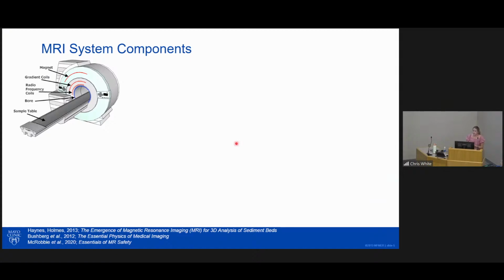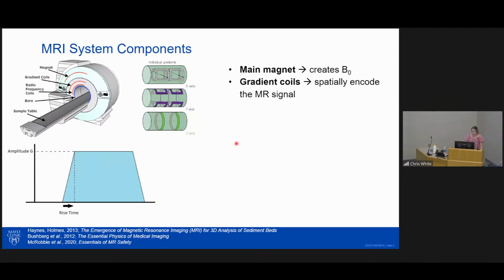So there are three main components of an MRI scanner that I'm going to talk about today. The first is the main magnet, which creates the very strong static magnetic field called B0. The second are the gradient coils, and these are used to provide the pulses to spatially encode the MR signal. So there are three gradient coils, GX, GY, and GZ, and gradient pulses usually have a trapezoidal waveform as seen in this figure. So two characteristics that define these pulses are gradient amplitude and slew rate. And slew rate just means how fast a scanner can switch the gradient amplitude.